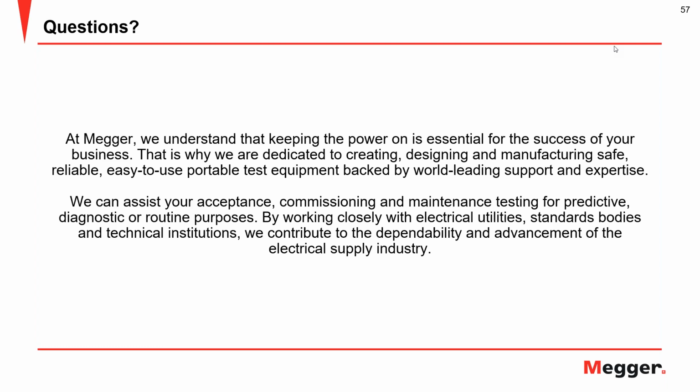Well, if you look on, I think, slide number 17, the standards mentioned on that slide are all standards for medium voltage cables. So I assume what the person asking the question means by low voltage cable is 600 volt cable.